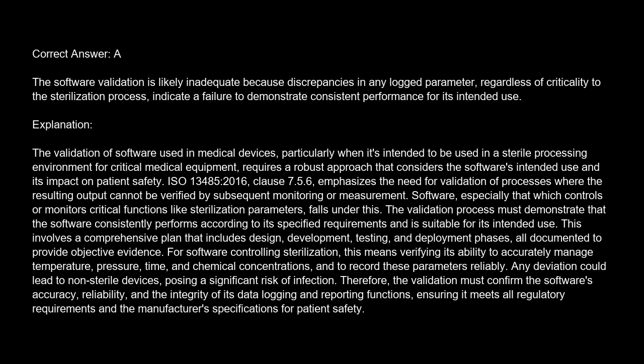Correct answer is A. The software validation is likely inadequate because discrepancies in any logged parameter, regardless of criticality to the sterilization process, indicate a failure to demonstrate consistent performance for its intended use. Explanation: the validation of software used in medical devices, particularly when it's intended to be used in a sterile processing environment for critical medical equipment, requires a robust approach that considers the software's intended use and its impact on patient safety.